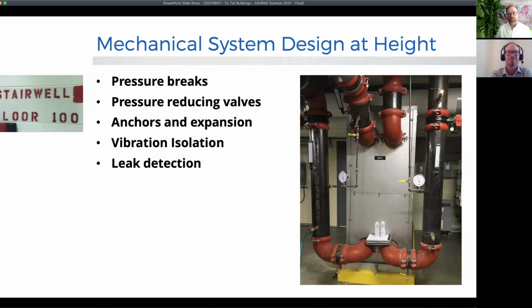Vibration isolation is something that comes into play a lot, especially when you have large mechanical equipment, and you might have a sensitive area below, beneath, or adjacent to. I work a lot in multifamily residential, so the most expensive unit is usually the one at the top of the building, right below all the expensive equipment that makes the most noise. Having an eye on making sure vibration isolation systems are there in the design, that the submittals look right, and that in construction they're implemented is important. There are some tests that sometimes we'll do with acoustical engineers as well in the commissioning process to make sure we're mitigating any kind of vibration and noise concern.